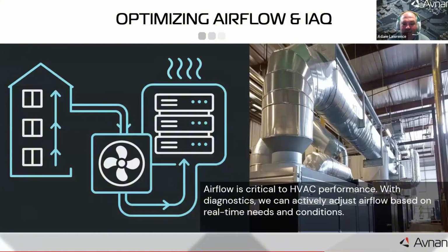Right sizing isn't only about cooling and heating capacity. Airflow is critical to HVAC performance, efficiency, and indoor air quality. Now, with diagnostics, we can actively adjust airflow based on real-time needs and conditions. For instance, if your controller detects that the temperature delta across the coil is smaller than expected, it can decide to adjust the blower speed to allow more heat exchange and better dehumidification. This kind of demand-controlled ventilation and airflow is increasingly expected. Standards like ASHRAE 62.1 encourage, and in some cases require, dynamic ventilation control to maintain air quality without wasting energy.